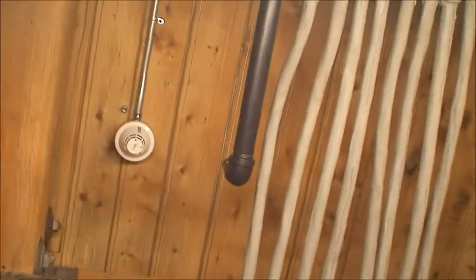This is a system smoke detector, same as in the corridors. You can tell the difference between those and the unit smoke detectors, the ones you get at home. Yeah, exactly. So the chirping you heard, was it the fourth floor? We should just check it out. How often do the batteries need to be replaced in individual units for the smokes? Same as your house, like a year, but every 6 months, really. These are not battery. Those are hard power to the building, power to the fire alarm panel, 24 volt. So we do not need to replace those. No, don't need to replace those. So units, annually?